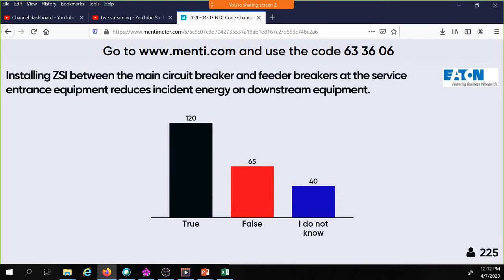Installing ZSI between the main circuit breaker and feeder breakers at the service entrance equipment reduces incident energy on downstream equipment. We got a lot of work today. This is why I think it's going to take 2 hours right here. These last 3 questions.